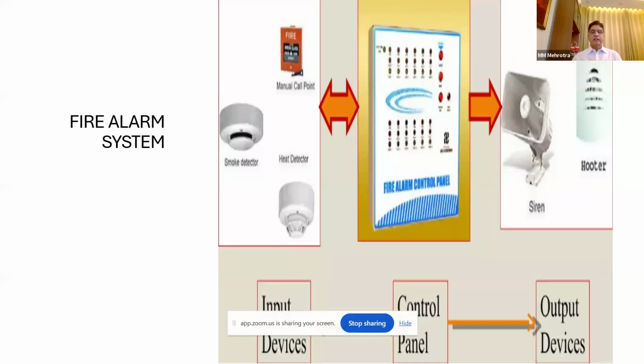Now, this figure also shows control panel is given signal from input devices. Control panel gives output to output devices. Output devices are my siren and hooter. Normally, fire alarm system is not required to operate any firefighting system. Firefighting is different. Fire alarm is different. Fire alarm is totally electric, like internal electrification, something like that.